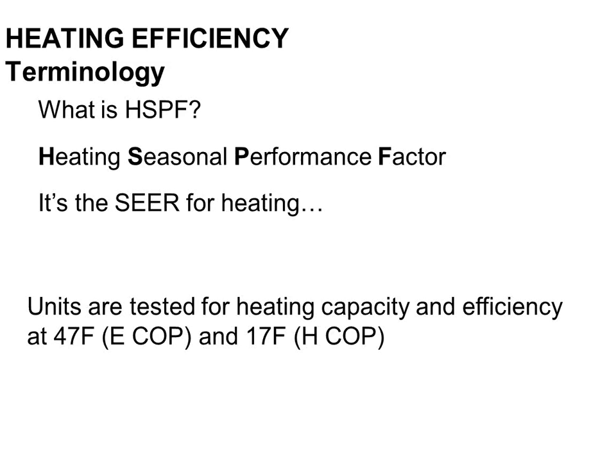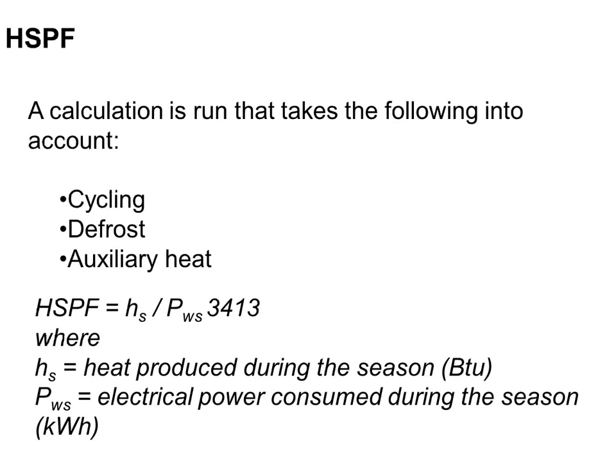Because we recognize the fact that the capacity of the heat pump drops as the outdoor air temperature drops, all heat pumps are rated at two temperatures. They're rated at the 47 degree, and they're also rated at a 30 degree lower temperature, which is 17 degrees Fahrenheit. That way you can see how the capacity is dropping off as it gets colder outside. So you really need to look at both those numbers to see if things are going to happen the way you want. You should know that HSPF isn't a straight up efficiency number. It is a seasonal type number.